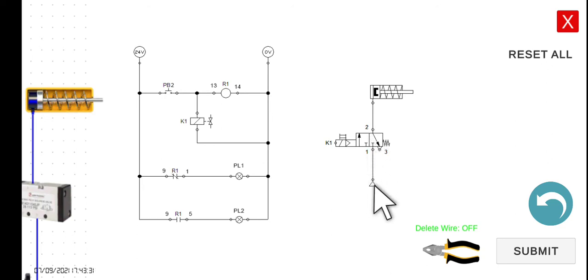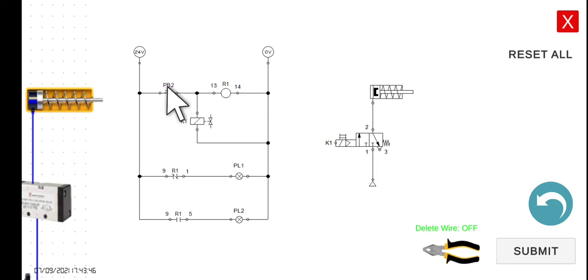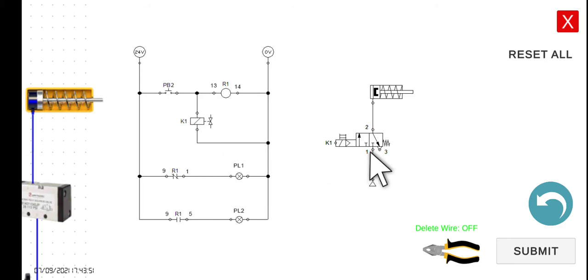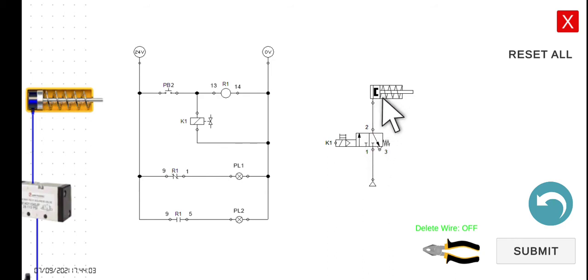The solenoid will allow the high pressure air to flow through to the pipe, and then the high pressure will extend the cylinder. However, if we release the button, the solenoid will be deactivated. It will return to its original state with the help of the spring return. The air pressure will no longer flow through the solenoid and the cylinder, so it will go back to the retract position.